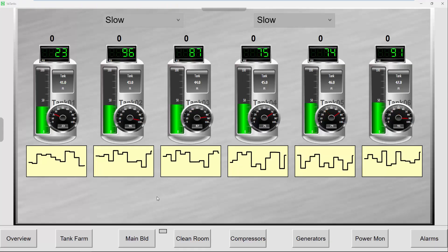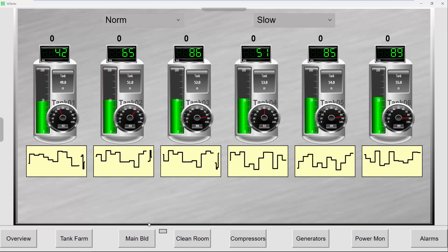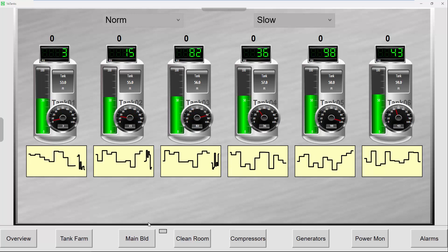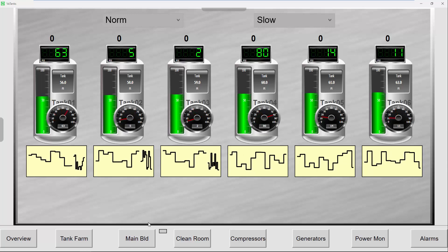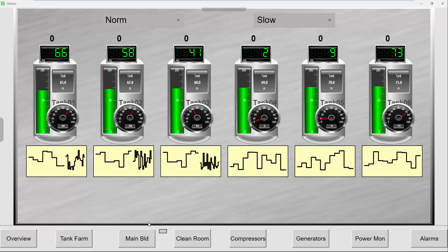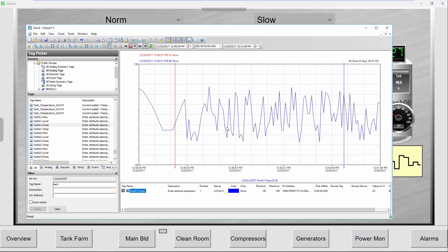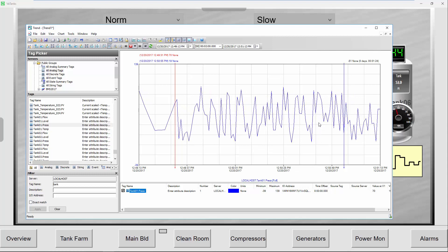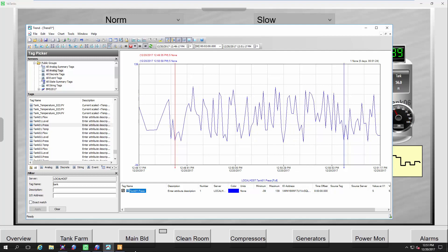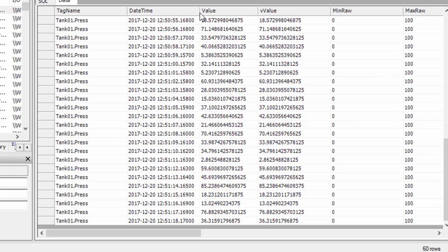Now I'm going to change the pull rate for the first three tanks to a normal mode, which is one-second resolution. Right now we're pulling from a simulation IO server - this could very well be an Allen Bradley driver or some other PLC type. You can start seeing on the thumbnail trend that the resolution of data collection is much quicker. If I look at the historian client trend, it's updating a lot more often than before. In the query tool, the data is truly coming in every second - 11, 12, 13, 14, 15 - every second.